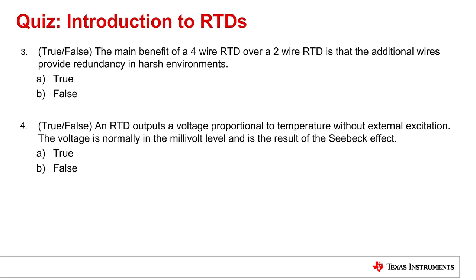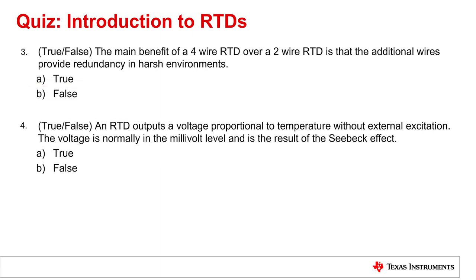Question 3: True or false — the main benefit of a four-wire RTD over a two-wire RTD is that the additional wires provide redundancy in harsh environments. The correct answer is B, false. The main benefit of a four-wire RTD is higher accuracy that results from automatic lead resistance cancellation. Question 4: True or false — an RTD outputs a voltage proportional to temperature without external excitation, with the voltage normally in the millivolt level as a result of the Seebeck effect. The correct answer is B, false. An RTD requires external excitation, and the Seebeck effect describes the behavior of a thermocouple.